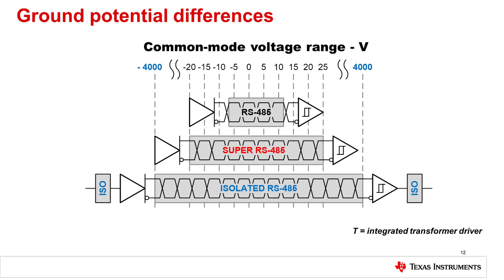When grounding an RS-485 system, the ground potential difference should not violate the common mode specification for the transceiver, which the RS-485 standard specifies as at least negative 7 volts to positive 12 volts. Some transceivers support even higher voltages, from negative 20 volts to positive 25 volts. In cases where very large ground potential differences could occur, an isolated RS-485 transceiver should be used.